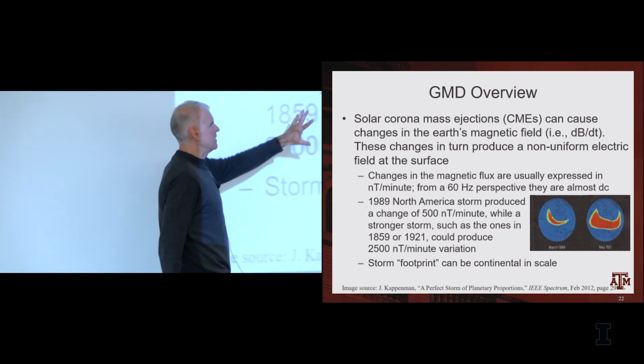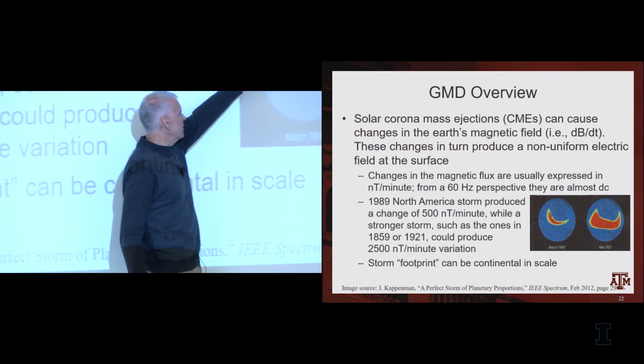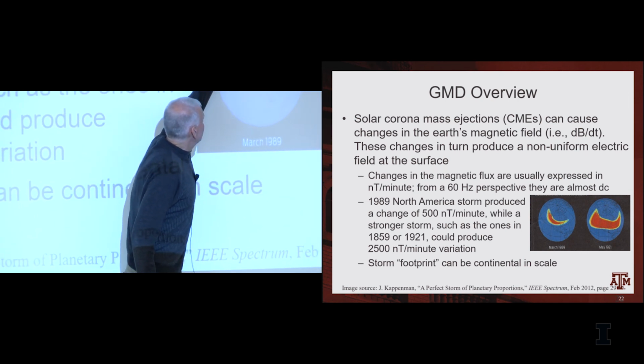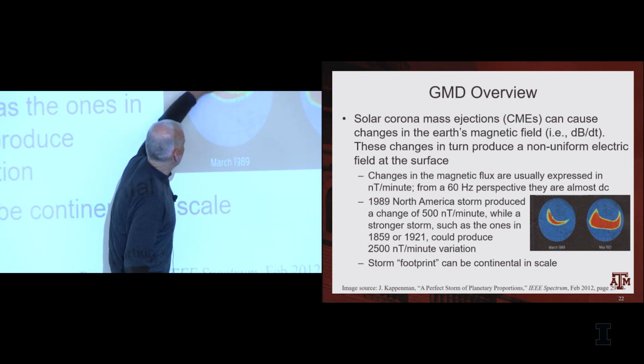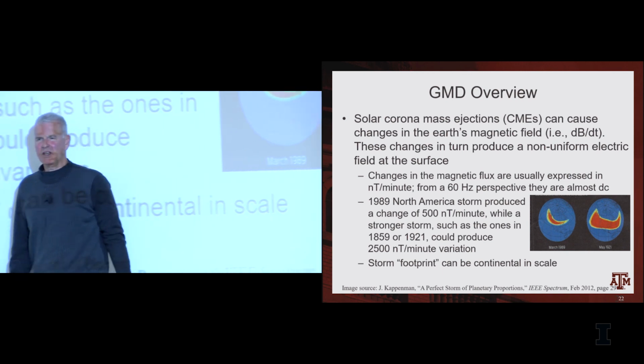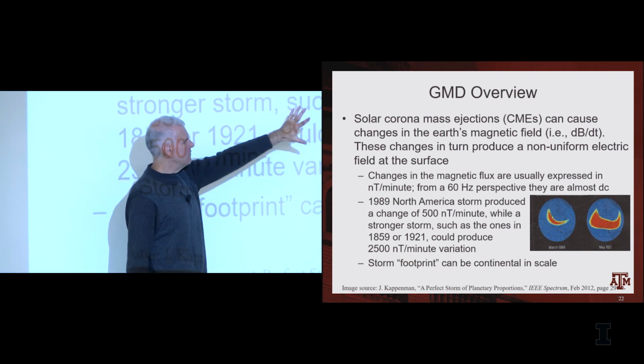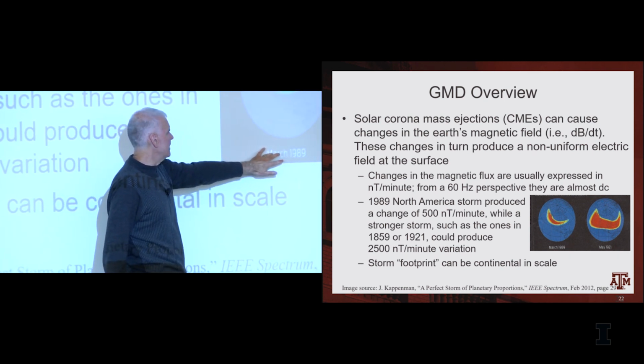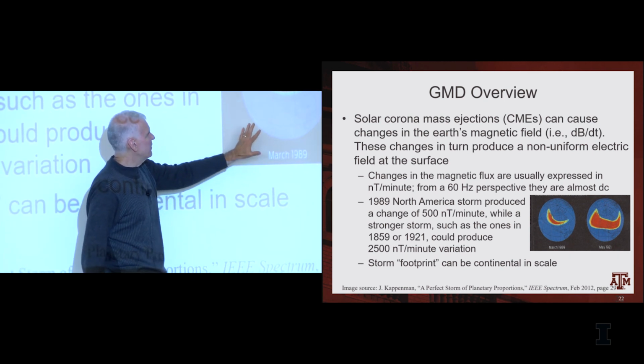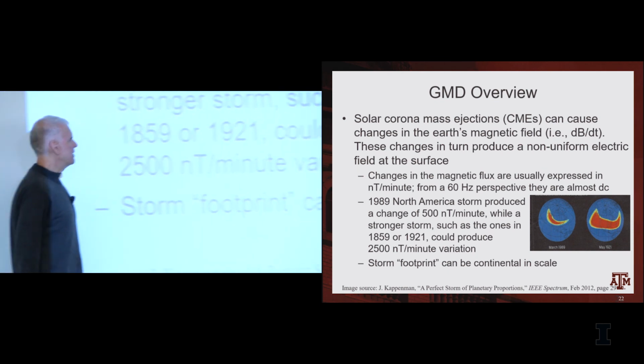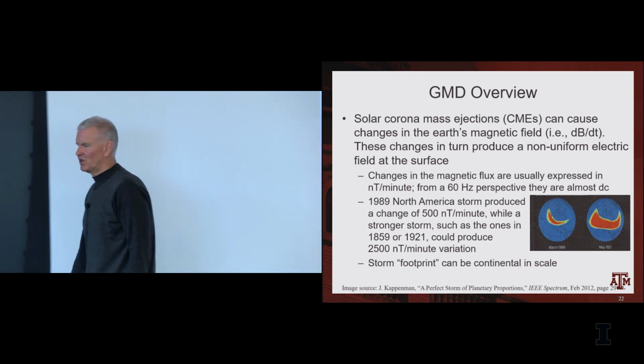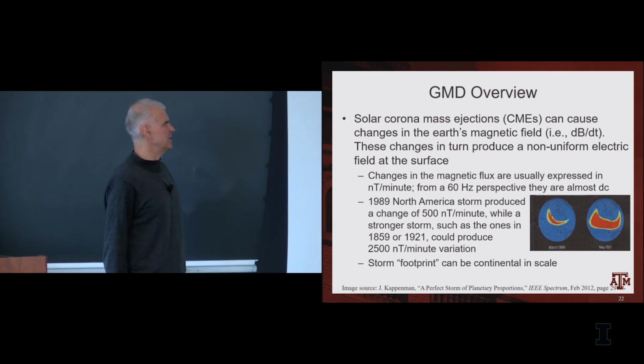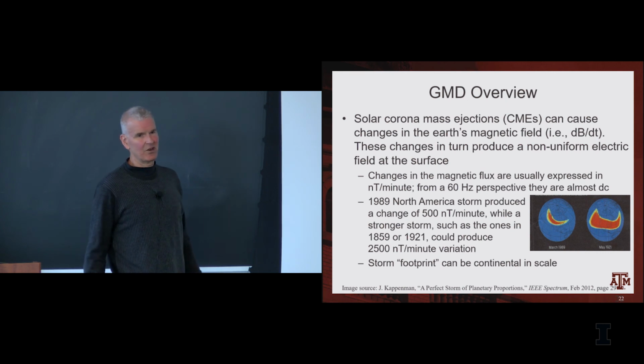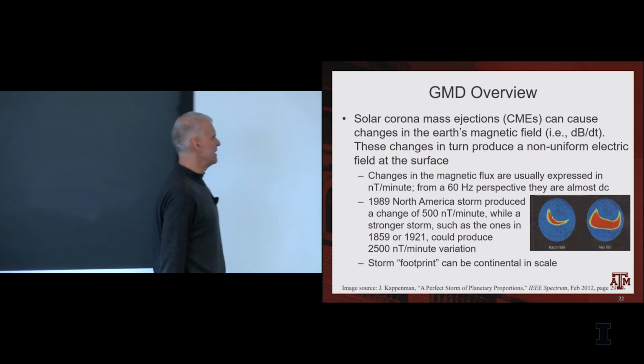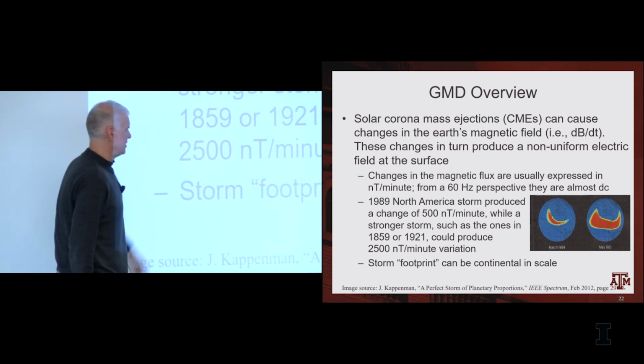This visualization right here shows a GMD that occurred in March 1989. This is the Earth. This part right there is North America. That crescent shape covered a good chunk of the northern part of North America. This event caused the blackout of Quebec in 1989. It turns out that the Quebec event was relatively small compared to what we've seen in the historical record. In the historical record, we've seen storms that might be 5 times as large as the Quebec event. One occurred in 1859. Another one occurred in 1921.